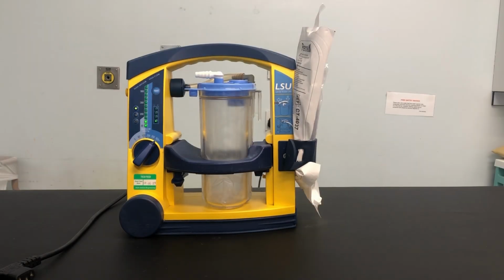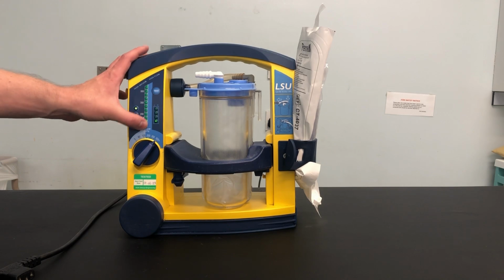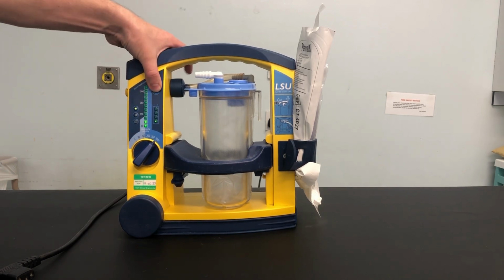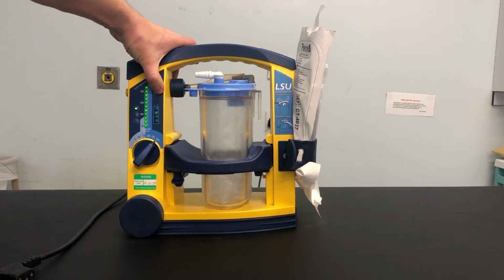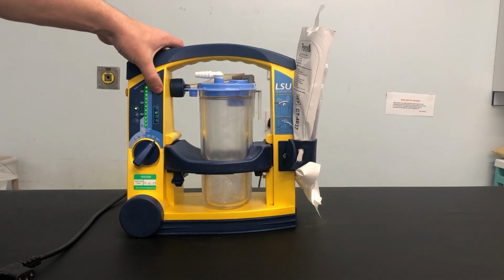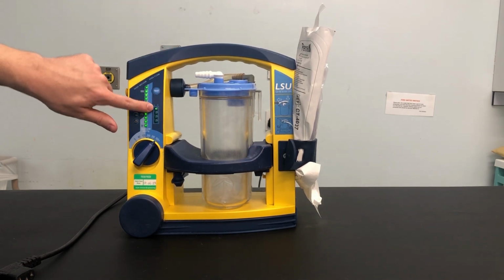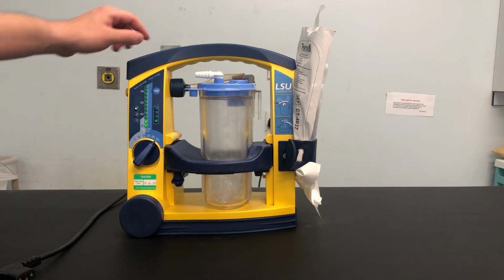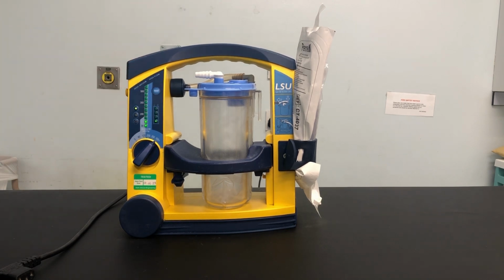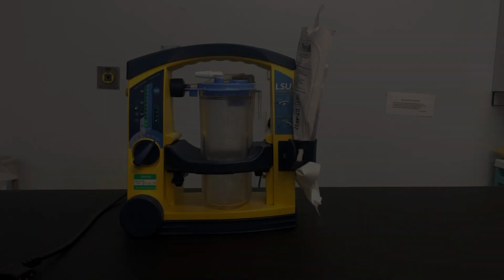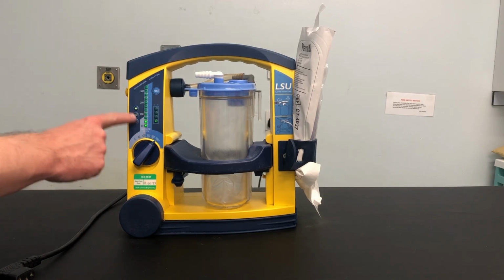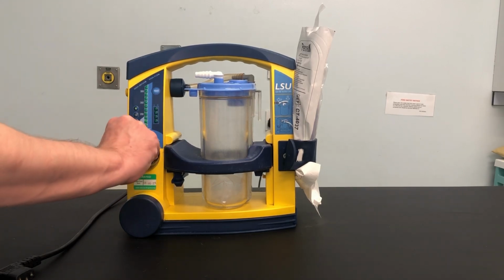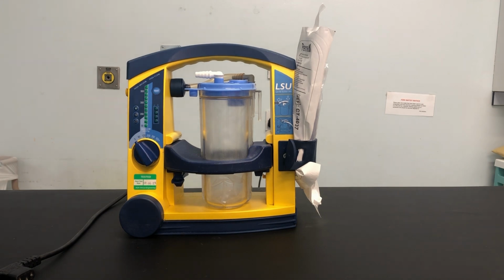After the test is completed, the vacuum indicator will automatically display the first result, occlusion. To display the other results, press the test button once for each test. If you continue pressing the button after the fourth test has been displayed, the earlier results will be repeated, i.e. 1, 2, 3, 4, 1, 2, 3, 4. To exit the test program, set the operating knob to off. Do not turn off the device until the results have been reviewed and no fail indicator light has been lit.